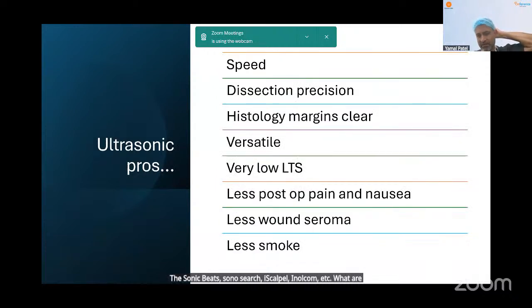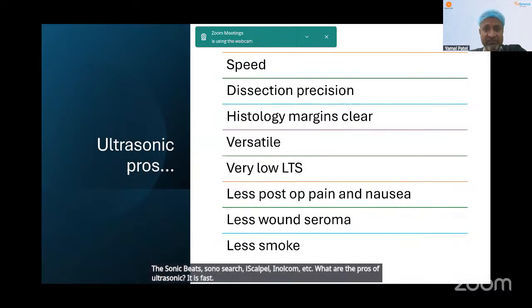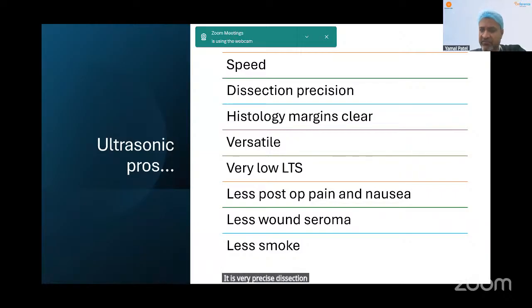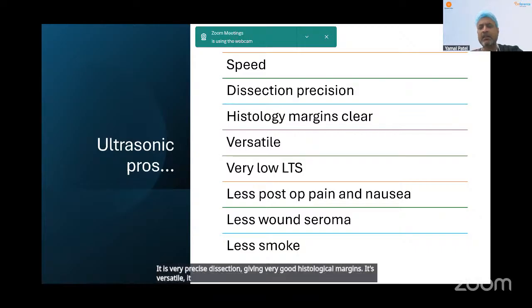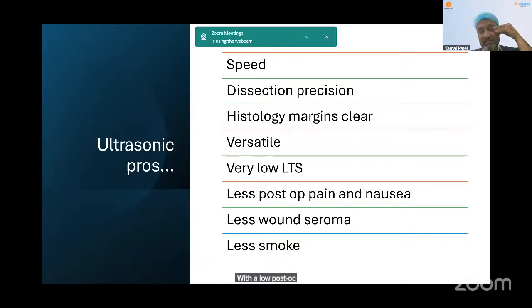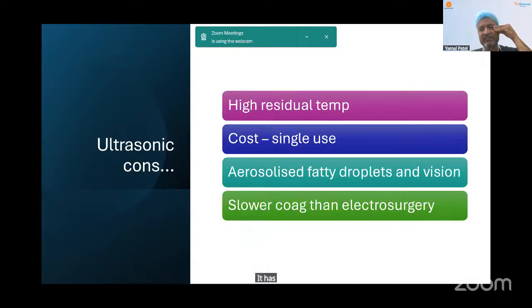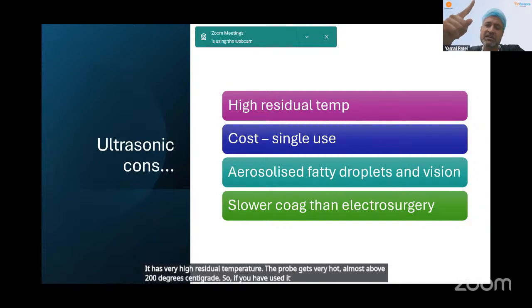What are the pros of ultrasonic? It is fast. It is very precise dissection, giving very good histological margins. It's versatile. It has a very low lateral thermal spread with a low post-op pain and nausea, less wound seromas, and less smoke. However, it has very high residual temperature. The probe gets very hot, almost above 200 degrees centigrade. So if you have used it and you touch the probe, even without activating it, to a bowel loop, it can actually easily burn that bowel loop because it's very hot for the first few seconds.